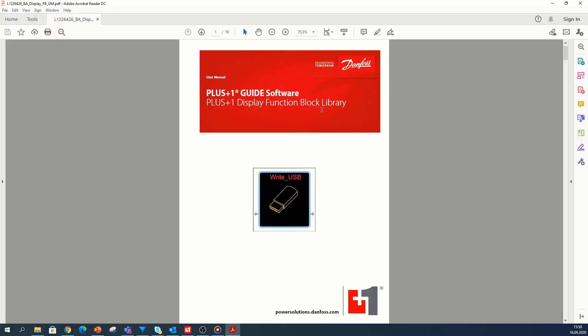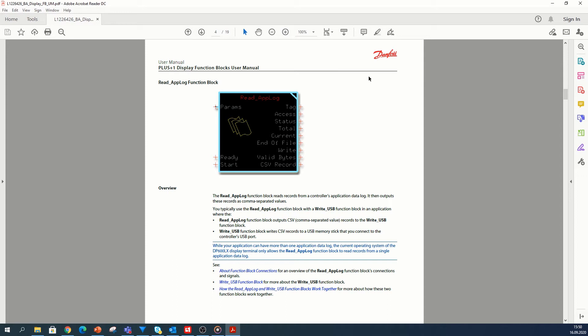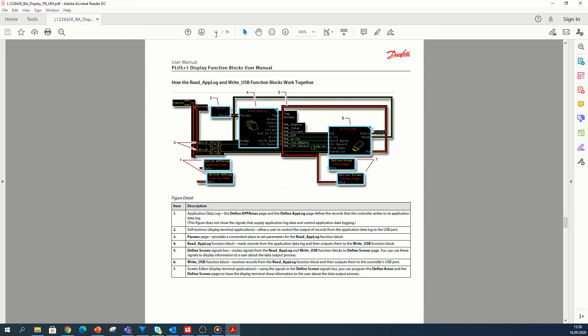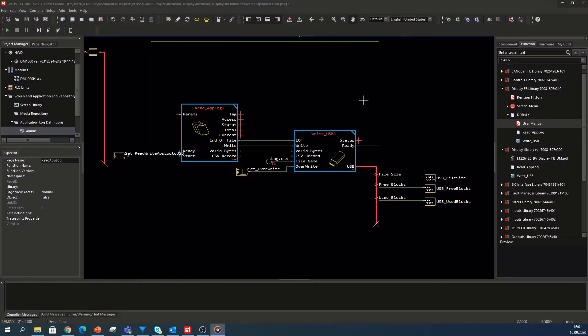The first function block is the read AppLog block. This block reads records from a controller's application data log and outputs these records as comma-separated values. The second function block is the write USB. This block writes CSV records to a file on a mass storage device, such as a USB memory stick that you connect to a controller's USB port. The display library also provides a user manual where each block is described in detail and how both blocks work together. As you can see on the following page, both blocks work perfectly together with just some little wiring and settings needed.